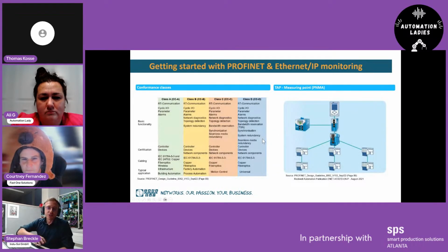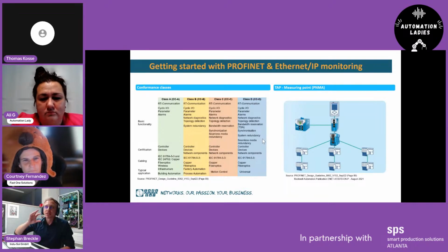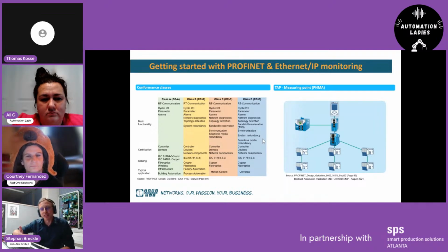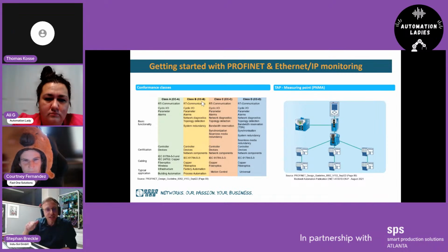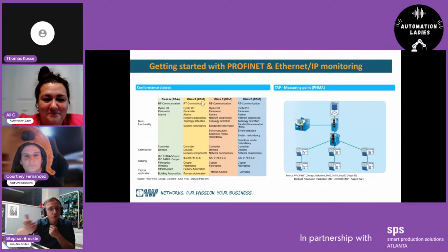Only that you know, and this is very important, if you run your OT system and think about preventive maintenance or maintenance at all, make sure the device supports some special features. In PROFINET that's not so critical, because normally if you use conformance class B devices, the device supports SNMP and LLDP. SNMP means Simple Network Management Protocol. That means you can request the device not only for IO information, but also for vendor information, firmware information, and security information, if we speak more about these features in the future.